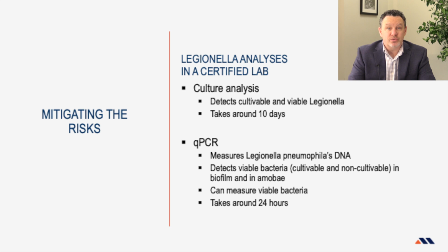So with regards to the tests that are available for Legionella specifically, there's enough material to have 3 or 4 webinars just on the testing protocols. But at a basic level, there are 2 different types of tests. There's the culture test, which is essentially a petri dish, and those will give you results within 10 to 14 days of viable bacteria. The secondary test, which I consider probably a more important test, is called a PCR, so quantitative PCR. Now, it can also test for living bacteria, but it can test for dead also, and there's ways to test for both.